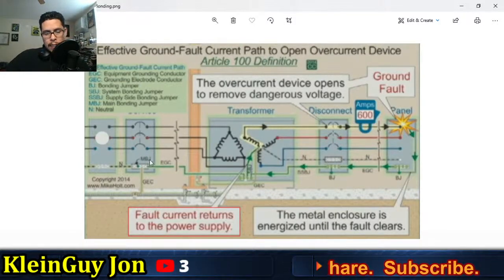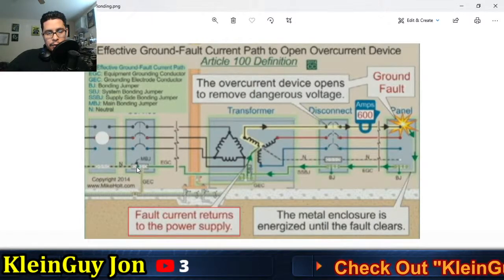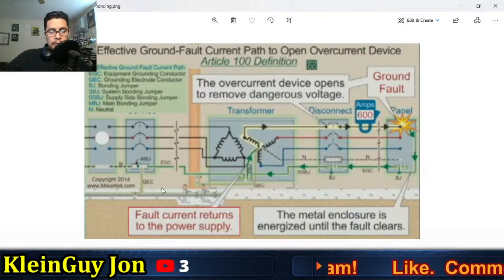and local codes. Now you have your equipment grounding conductor. You got a main bonding jumper. So this main bonding jumper right here is now tied into your neutral. You want to bond your ground, your main bonding jumper from the neutral to the casing, right? Then you have your grounding electrode conductor also bonded to your neutral, going to ground or to a case, or either a ground ring if you got a ground ring around the building, or if you got a rebar that can be used or listed as a grounding electrode conductor. That's fine.